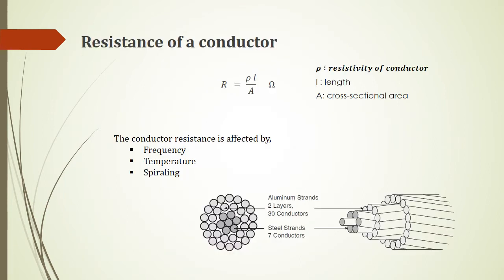First, the resistance of a conductor is given by R = ρL/A, where ρ is the resistivity of the conductor, L is the length, and A is the cross-sectional area. The conductor resistance is affected by the frequency of the AC current and the temperature of the cable.